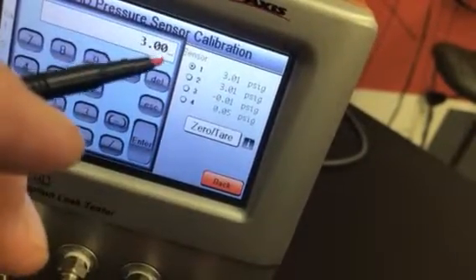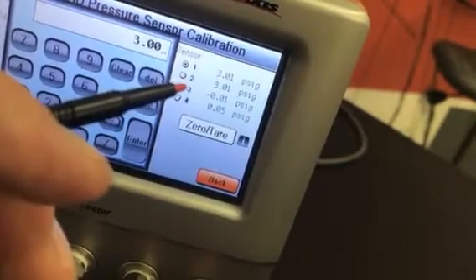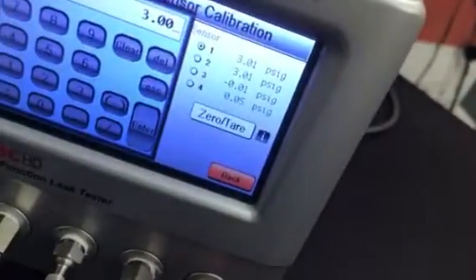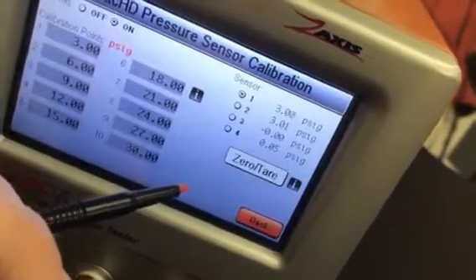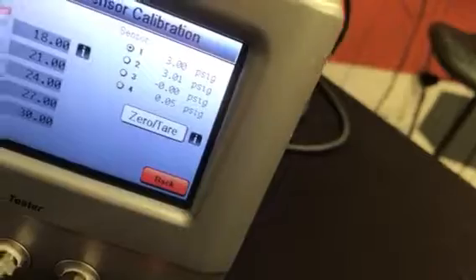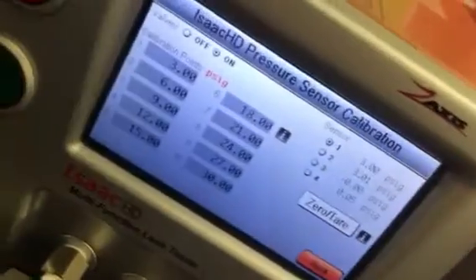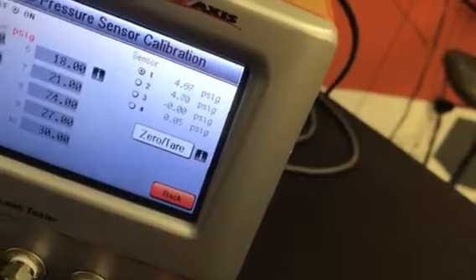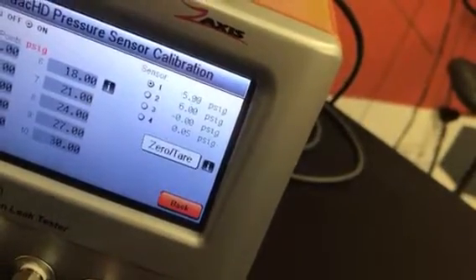I'm going to tell the tester number 1 sensor is at 3 PSI, and I know this because my number 2 sensor, which I'm reading off of, just like you're going to be doing with this, says 3 PSI. So by pressing enter, it just took that cal point. Now sensors 1 and 2 are 3 PSI. So to move on, now I'll see the next one, 6 PSI. I'm going to turn the regulator, get everything up to 6 PSI. And now do the same thing. I would touch number 2, the screen pops up, press enter, and so on.